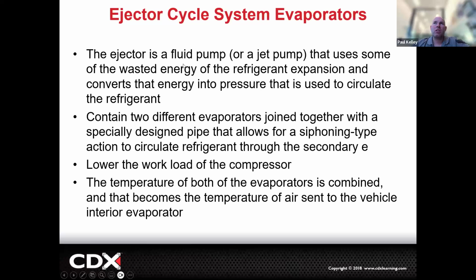The ejector is a fluid pump, and it uses some of the wasted energy from the refrigerant expansion, converting it into pressure that's used to circulate the refrigerant. It's two different evaporators joined with a specifically designed pipe that allows for a siphoning action to circulate refrigerant through the secondary one. The main goal is to lower the workload of the compressor, and then the temperatures of both evaporators combine to become the temperature of the air sent out.